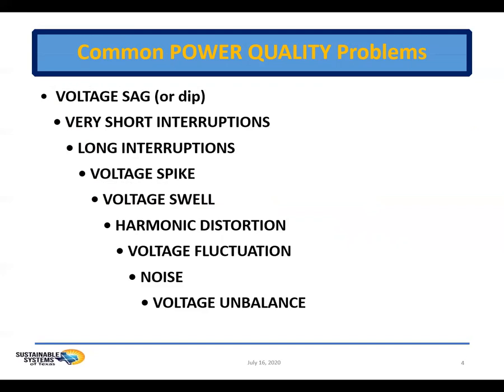Next are short interruptions. These are total interruptions of electrical supply for durations from a few milliseconds to 1 or 2 seconds. Then you have long interruptions. These are total interruptions of electrical supply for durations greater than 1 to 2 seconds. Next, we have voltage spikes. These are very fast variations of the voltage value for durations from several microseconds to a few milliseconds. And these variations may reach thousands of volts, even in low voltage. Next, we have voltage swell. This is a momentary increase of the voltage at the power frequency outside the normal tolerances with duration of more than 1 cycle and typically less than a few seconds.